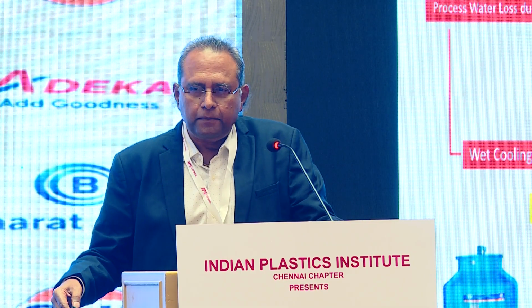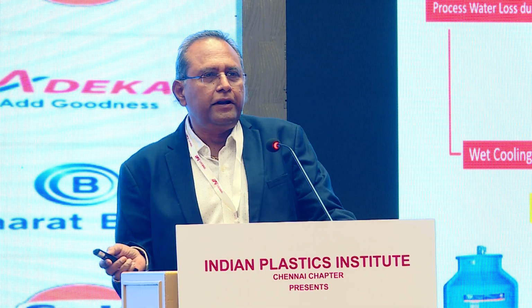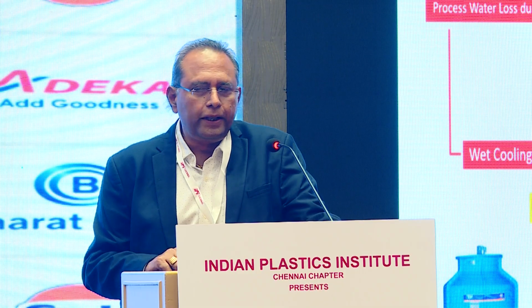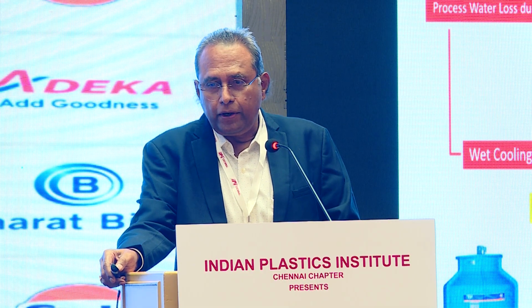Now types of cooling system. Basically cooling system can be divided into two. One will be a open cooling, another will be closed loop cooling. So open cooling means normally we have conventional evaporative coil type cooling tower, adiabatic cooling tower, that is typically an open cooling only in terms of evaporation, wet cooling tower and wet cooling tower plus dry combination. We have various options for conserving water. Then in closed loop, we have adiabatic cooling towers, dry coolers, and where some specific application calls for lower than wet bulb temperature, we need to go for chillers.